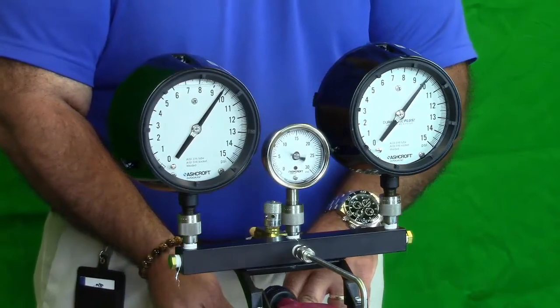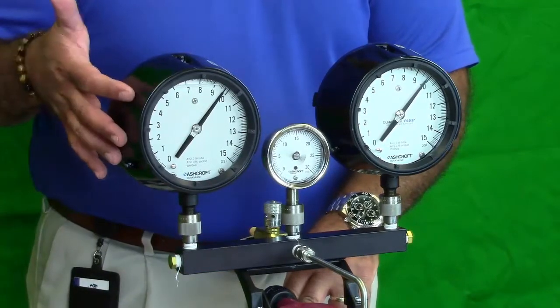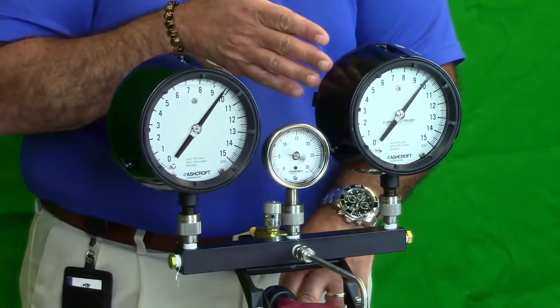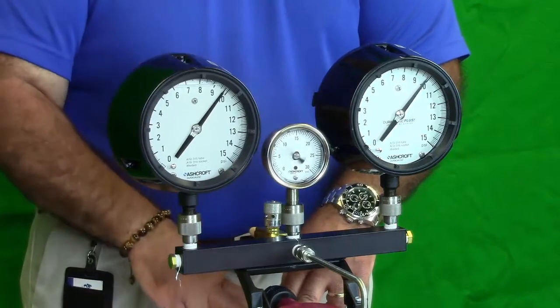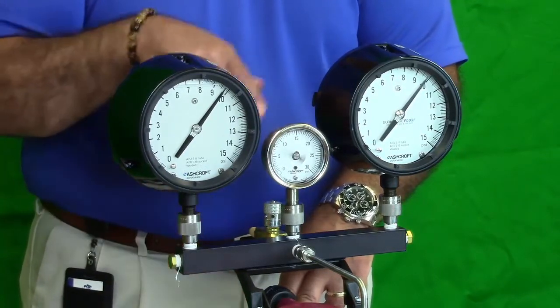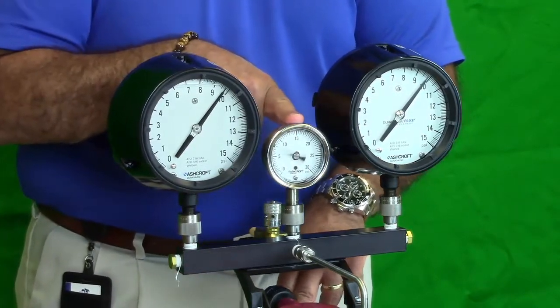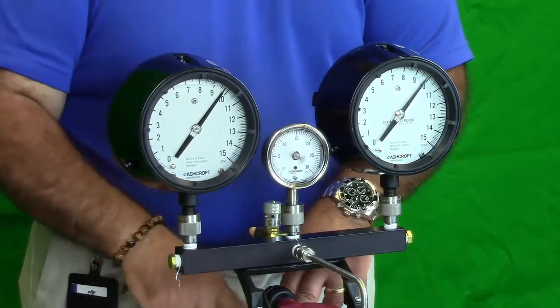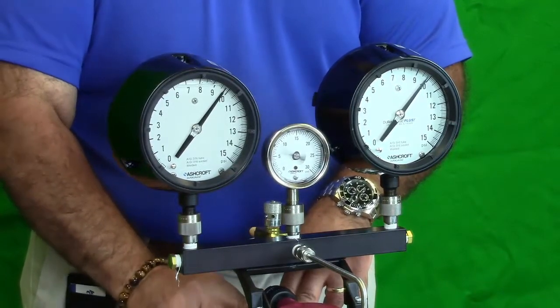As I turn this pump on, you'll notice that both the liquid filled and the Plus gauges are operating extremely smoothly, reducing the vibration and the pulsation, and our center gauge, which is uncorrected, is operating as it should, or as it would in that application.